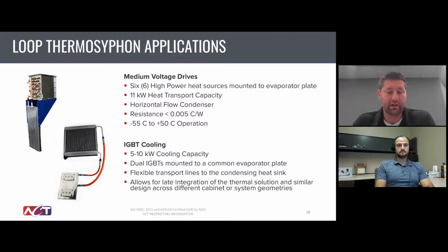That entire solution fit within a medium voltage drive cabinet with only the condenser exposed to the air environment. And then the bottom solution here, a similar type application. This was a 5 to 10 kilowatt cooling capacity. But what we're showing here specifically is the orange hosing that you see. And this was somewhat of what I was alluding to in the last example as well. You have the ability to have a remote condenser and flexible lines between the evaporator and condenser.